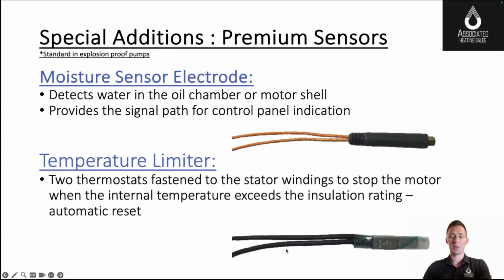The bottom is a temperature limiter. It's going to be in the windings of the pump, and it will turn the pump off if it becomes too hot. It'll allow it to cool down and it'll automatically reset. But in the meantime, it'll light up a light or sound an alarm in the panel, and the maintenance personnel will understand, hey, something's going on with my system.